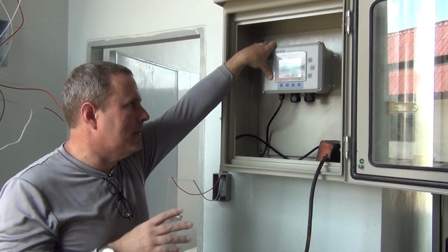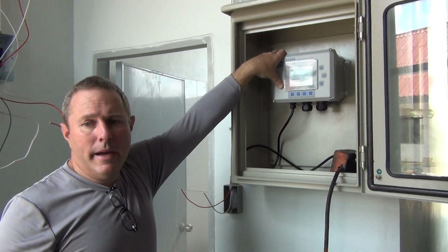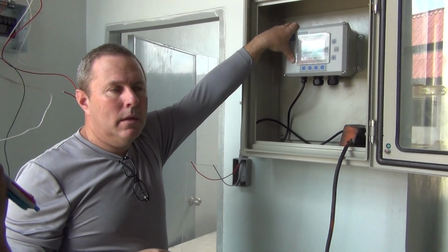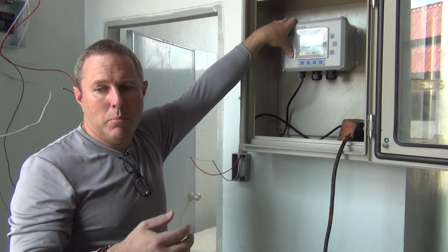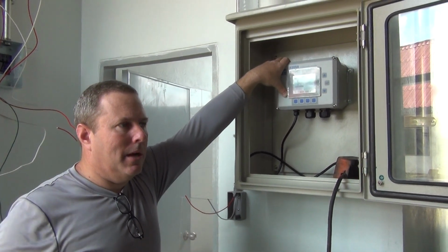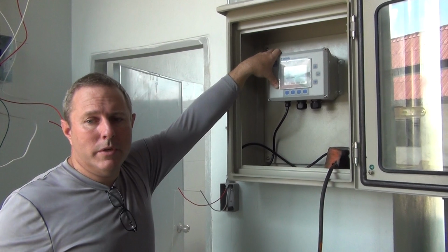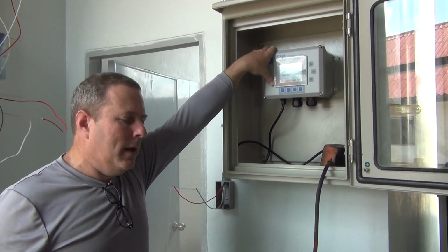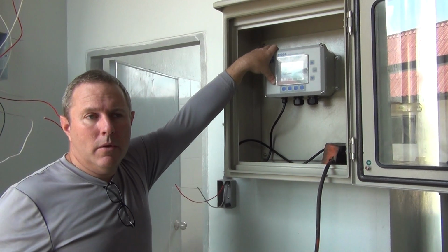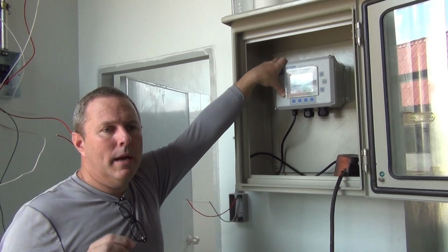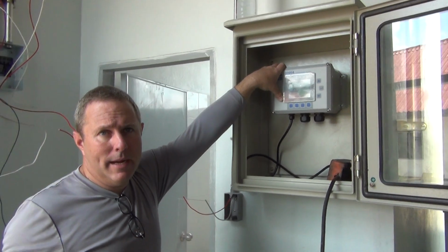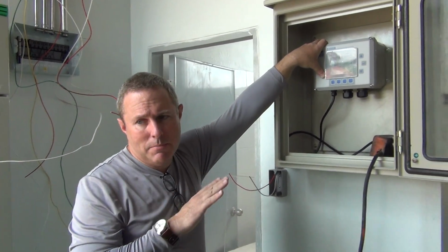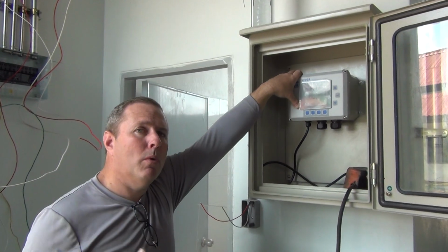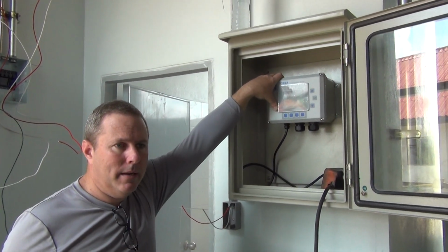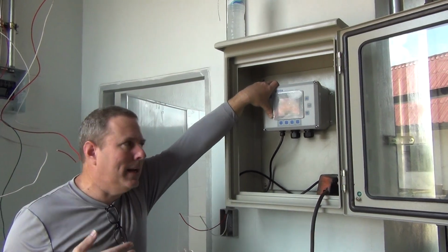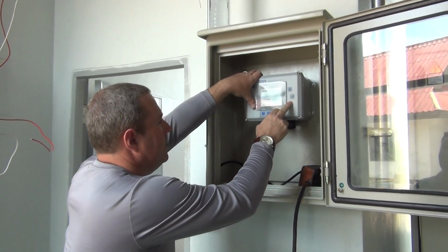There's another box like one of these called an IOEM 8, which is 8 circuits of input or output. There's also what they call an IOEM 4, which is 4 circuits of input or output. And then there's an REM 4, which is 4 relay outputs, and an REM 8, which is 8 relay outputs. You should not need anything for something so simple here, but later on, if you wanted to add other water quality monitoring aspects and be able to control and data log, then this would be where we would set them up.